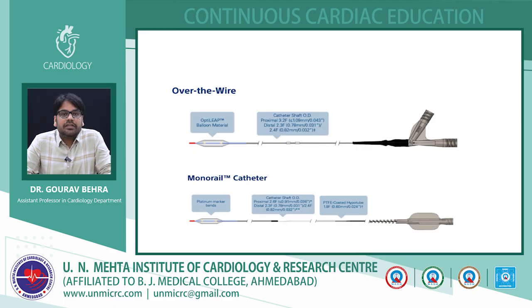So there are two types. One is the over-the-wire. Over-the-wire means, as you can see in this diagram, there are two separate ports at the distal end. From the angulated one you will inflate the balloon, and through the straight one the guide wire will come. That is the over-the-wire technique, mainly used for peripheral.